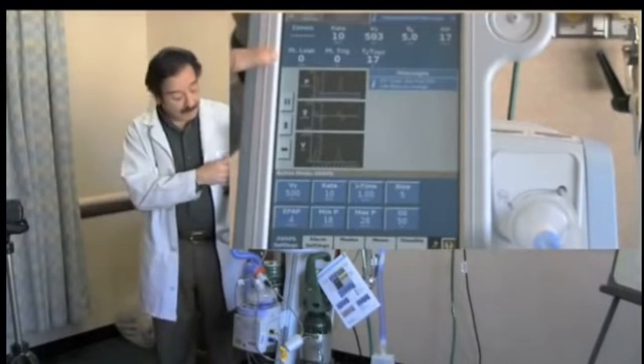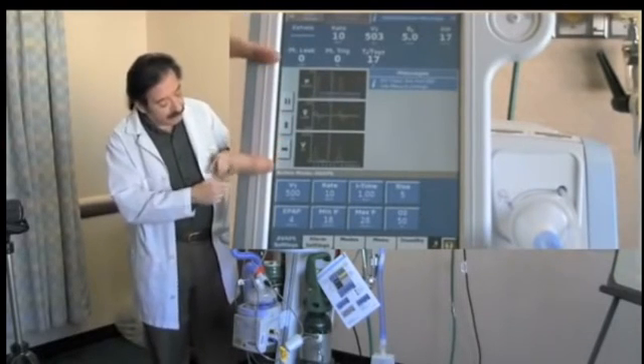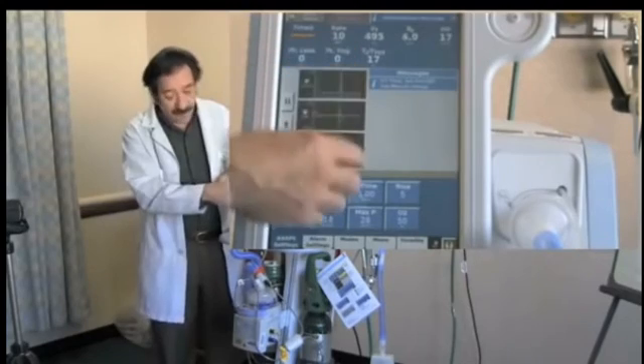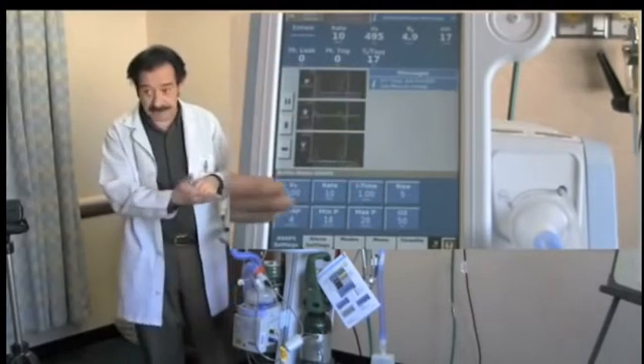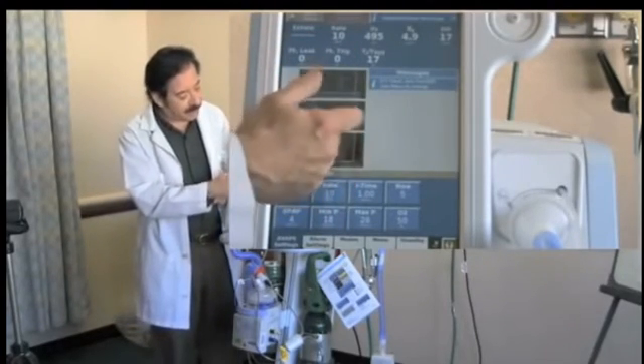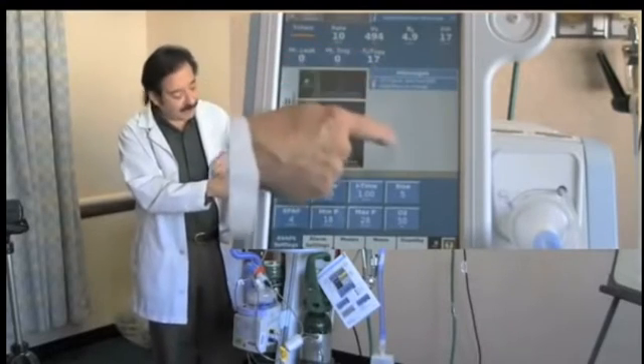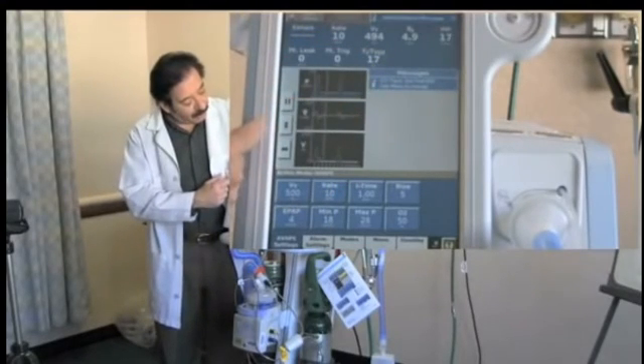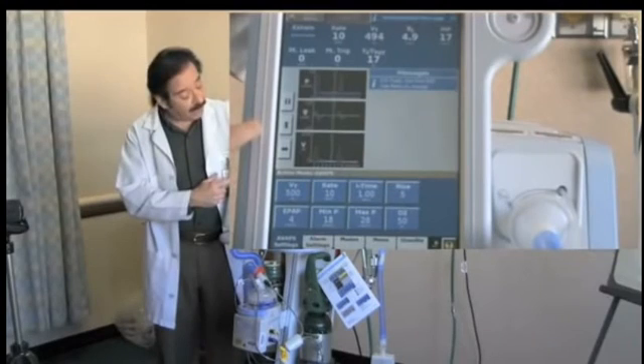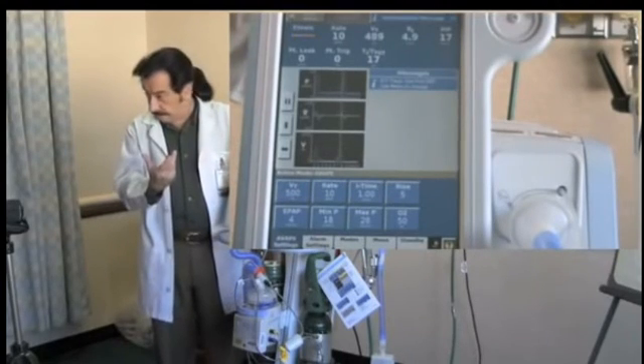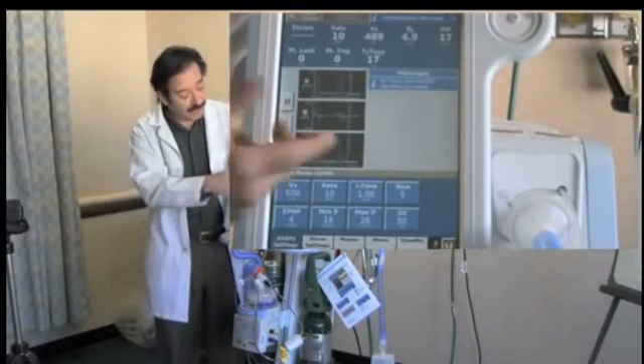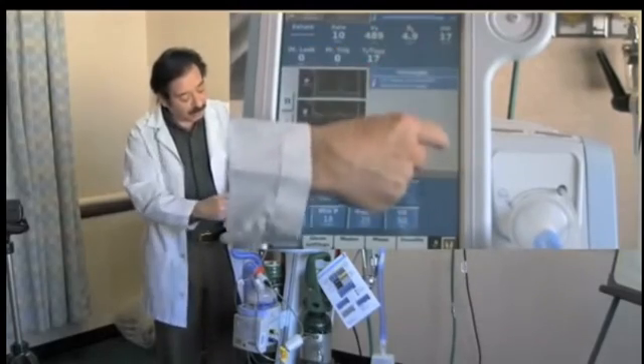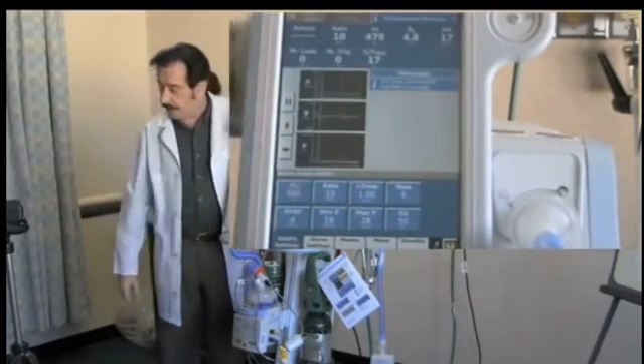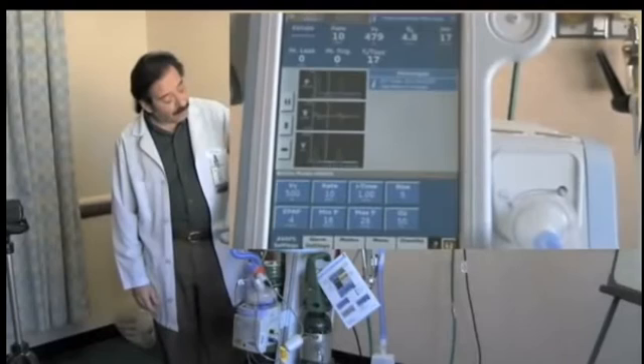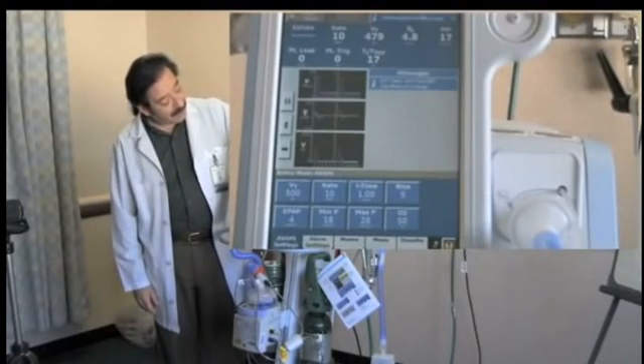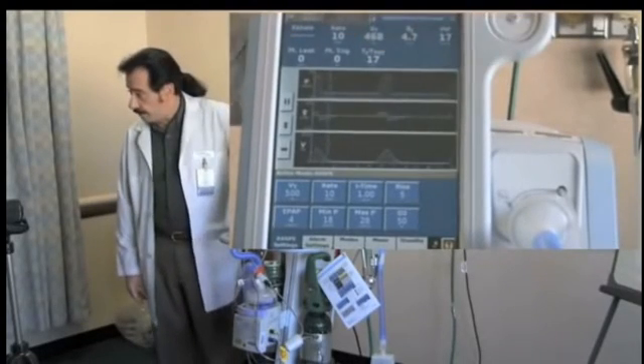It measures what the patient's doing. The third part is a shared panel with graphic waveforms, which are very functional on this device, unlike on the Vision, for instance, and historical messages. The message bar at the top right-hand corner gives you current alarms or information. Then historical data is stored in here, but it cuts off the graphic waveforms. So by hitting that bar, I restore my graphic waveforms.